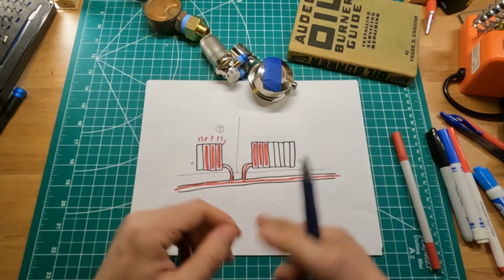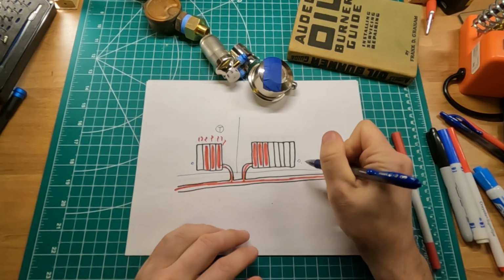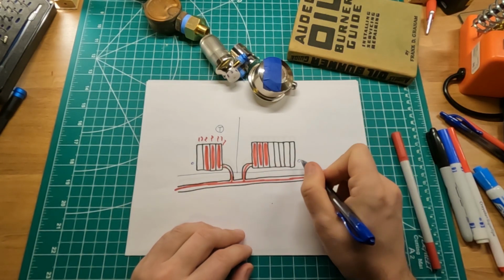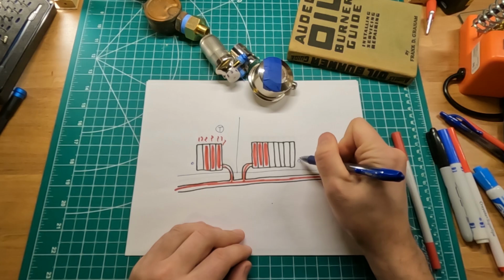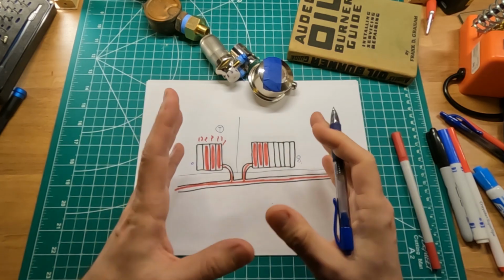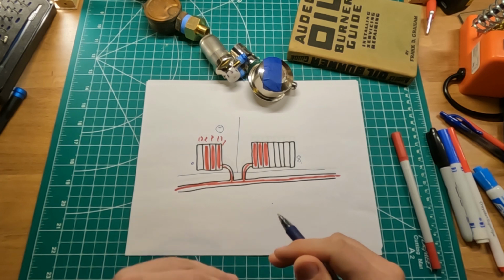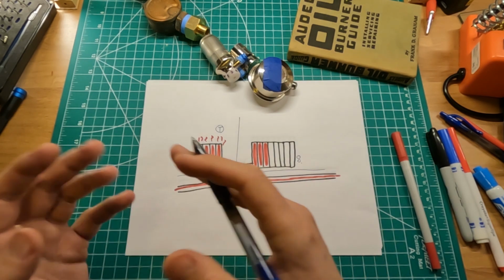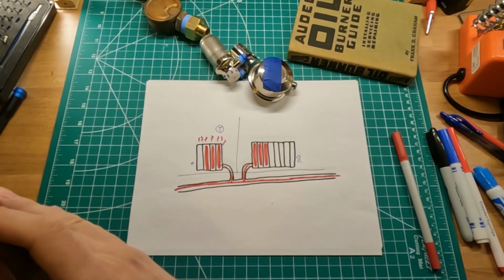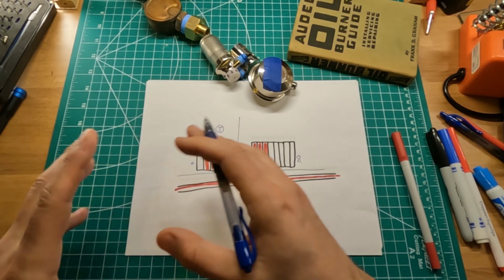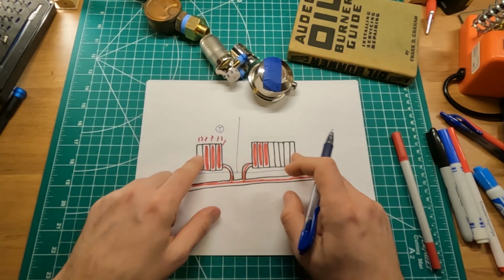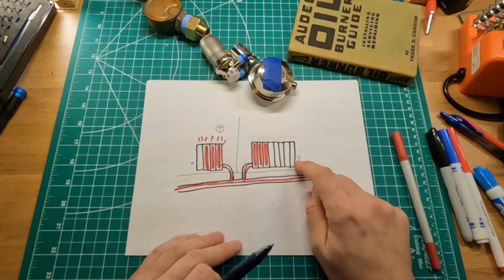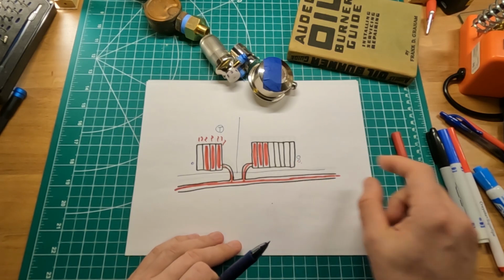Now I'm going to do it with drawing. Let's say we increase the air venting of this radiator by doubling it, with relative sizes obviously. If we redo the exact same scenario, the boiler starts producing steam and the steam enters those radiators. Now this radiator has double the size of the venting.